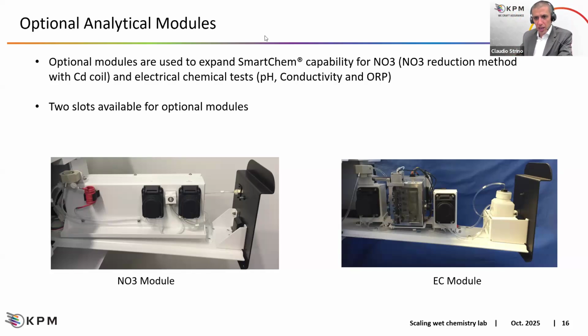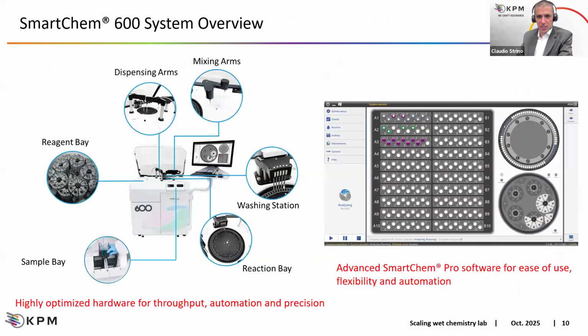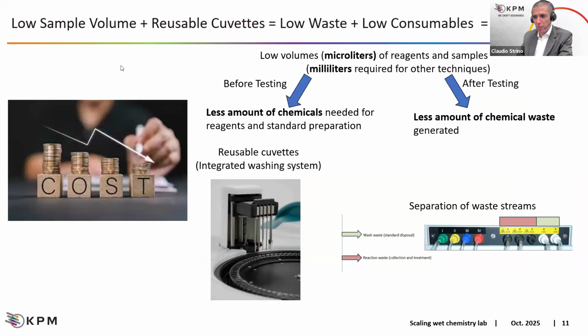Can the sample be separated by hazardous and non-hazardous reagent? Yes, this is one of the main plus points when we were speaking about cost saving, because we said already that all the SmartChem instruments are only generating liquid waste, and moreover, we can separate, thanks to a dedicated waste line, the normal standard disposal, so wash waste, from the reaction waste that needs to be collected and treated, and is only around 30%, 35% of the waste generated. The rest is normal wash waste.